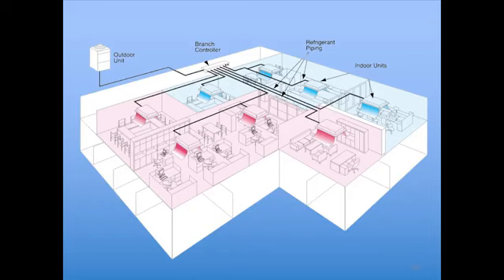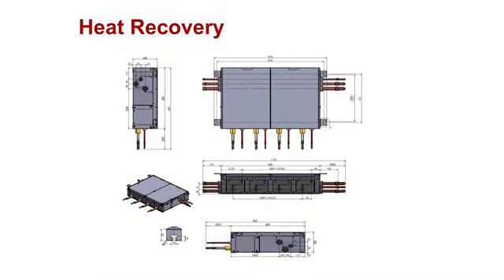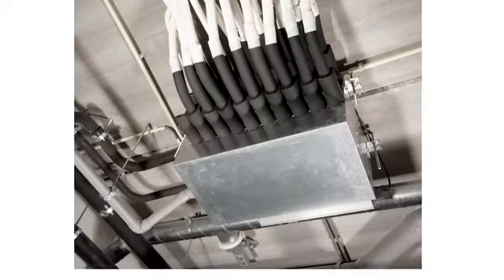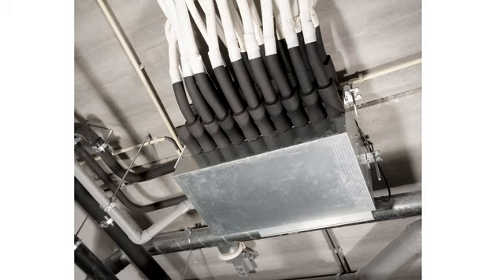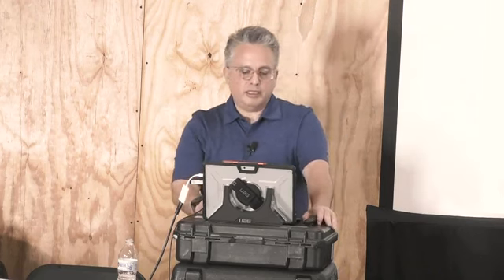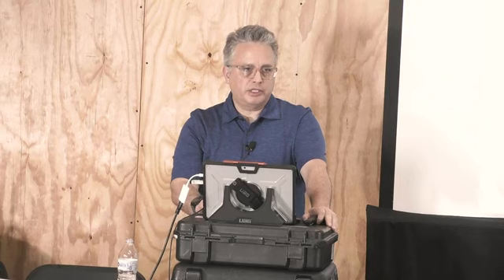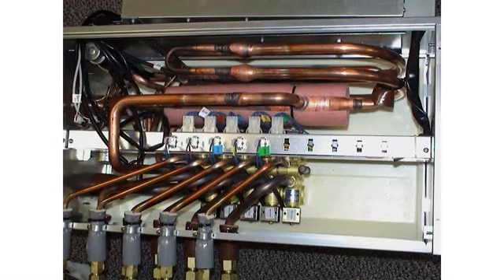This is an illustration of just one of the manufacturers that are available out there. Here's another illustration of a different one. They come in different sizes. You can have 1 or up to 16 indoor units connected. Here's a project. You can tell it's installed with 0 clearance at the top. I'm not saying that that's recommended, but you want to read the installation manuals for your prescribed clearances. And this is what that particular indoor heat recovery box looks like inside. You have a tube-in-tube heat exchanger here, your solenoid valves going to your ports, and your manifold block here. Then you have your LEV and its sensors.